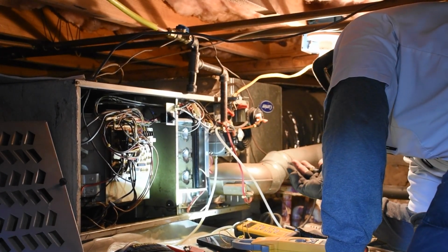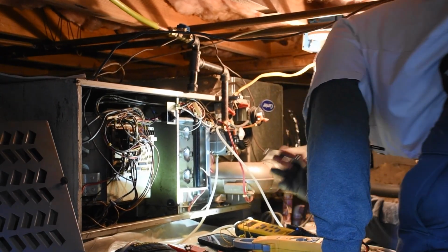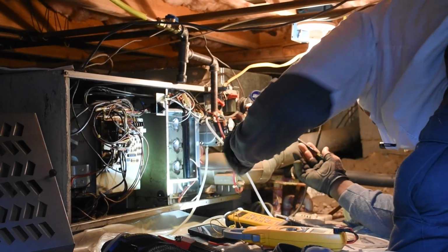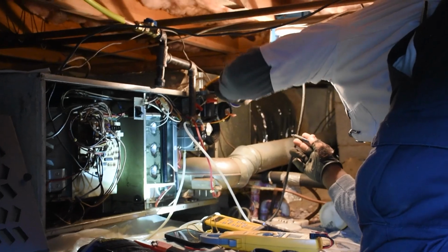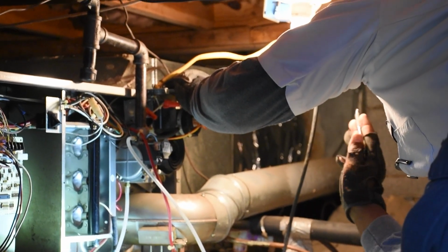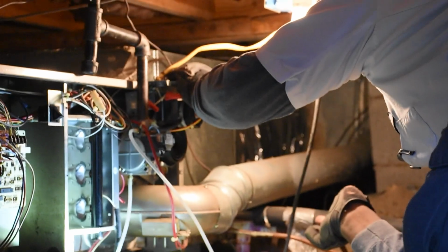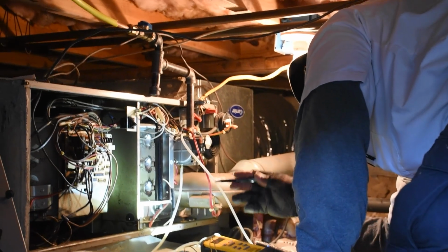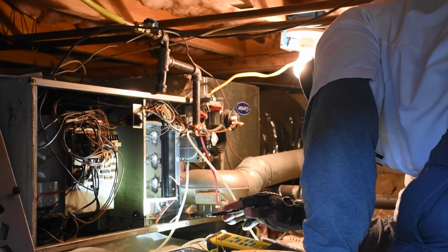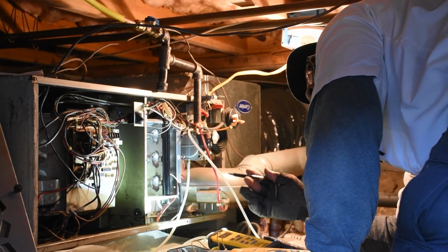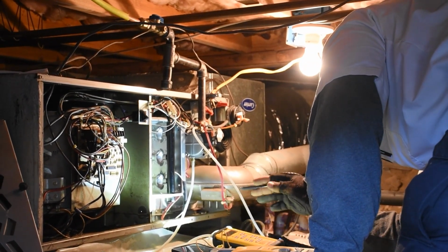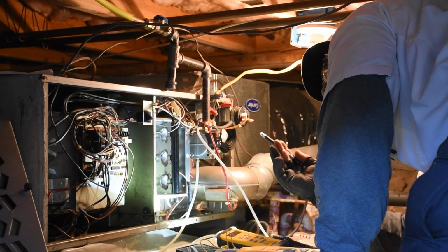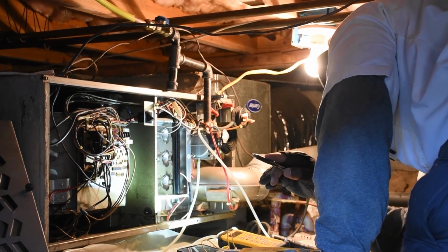And of course, this is a furnace AC setup. So you usually have the evaporator coil downstream from the furnace, which is facing that way going into the home. And beside the evap coil, you have the condensation pump, which in cases where you have, like, a 90% furnace, it uses a condensation pump, because you have a second layer of heat exchange which condenses, so it produces condensation even in the winter. So it would drain into a condensation pump, which ultimately would pump the condensate water out of the crawl space.